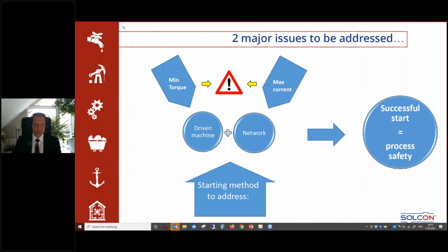Secondly, what is important, as I said, you have two issues. One is you need to have minimum torque so that the driven machine is started properly. On the other hand, you need to protect the network, because that is what soft starting is about. You need to protect the network with a maximum current. And in many cases, these two requirements contradict each other, and we need to find a good solution so that both requirements can be met. And if this is being done, you and customers have process safety.